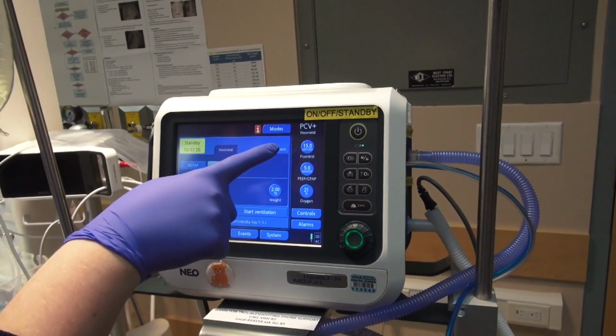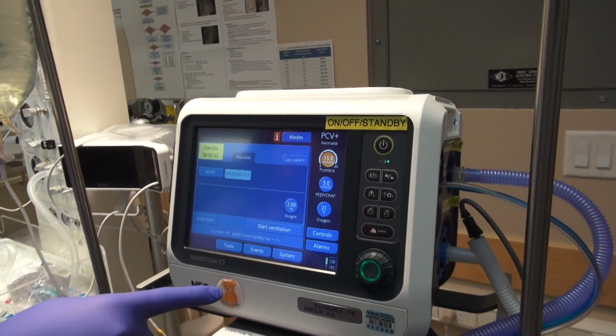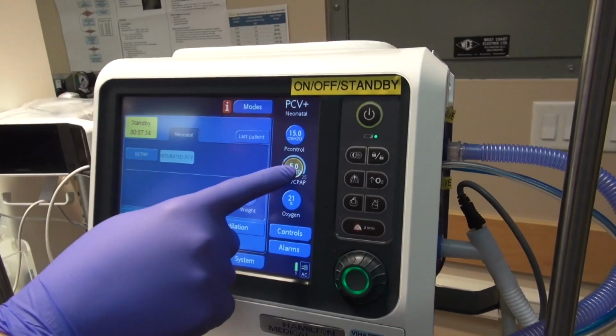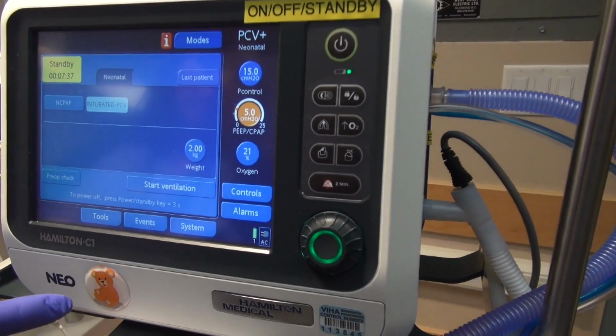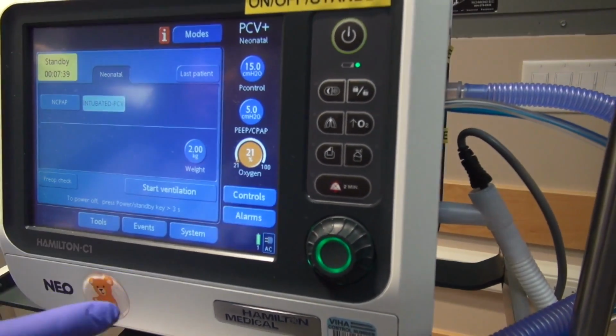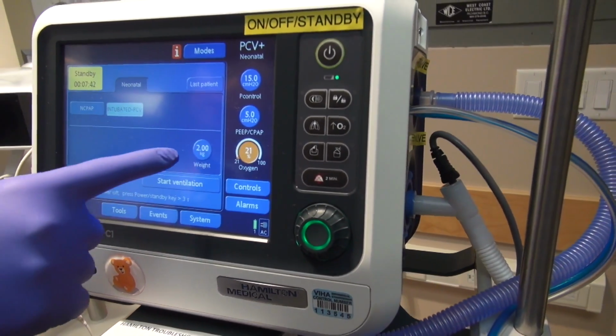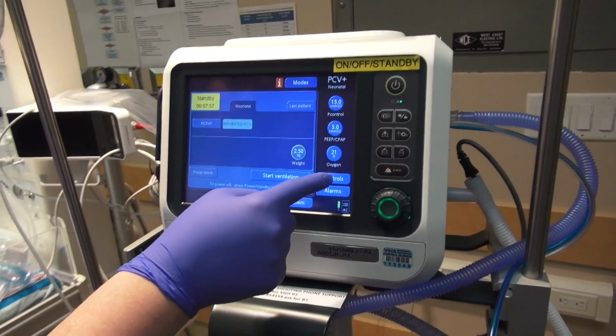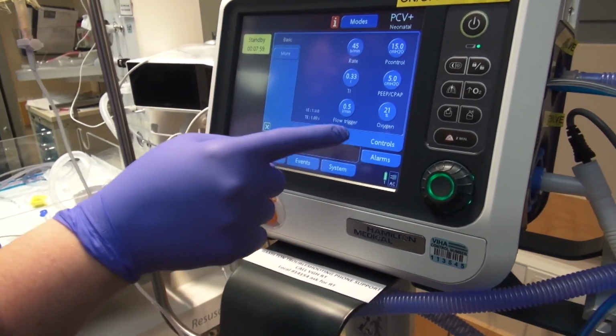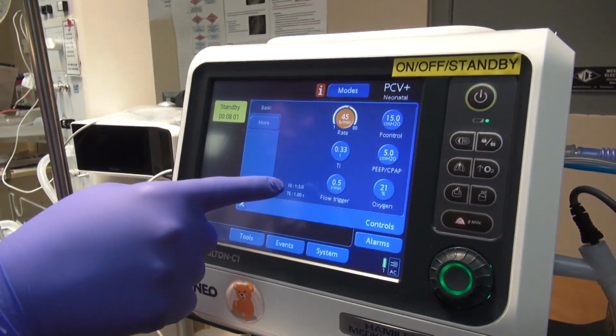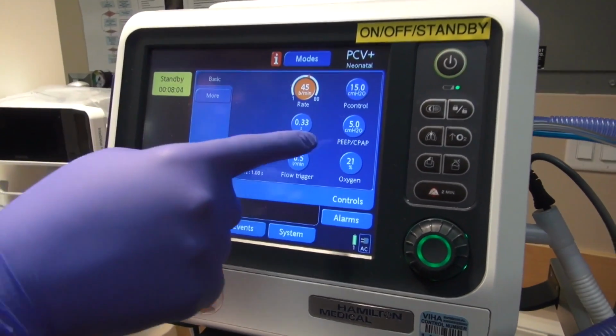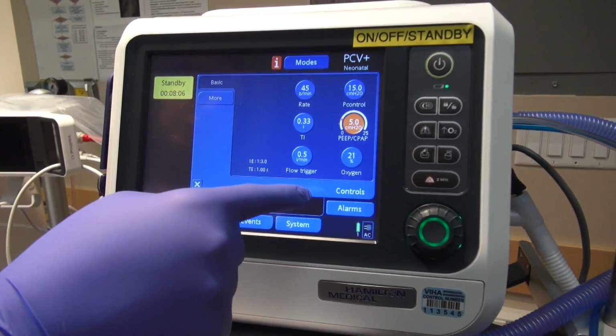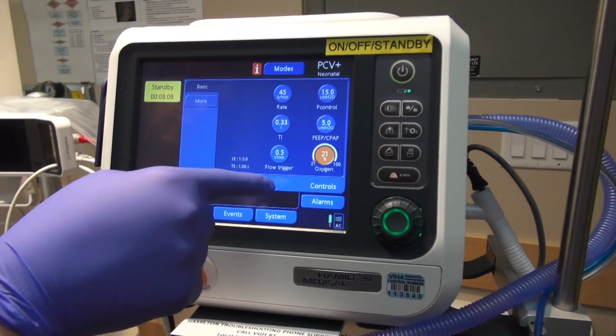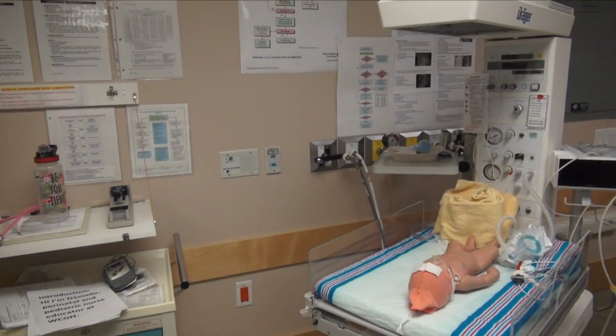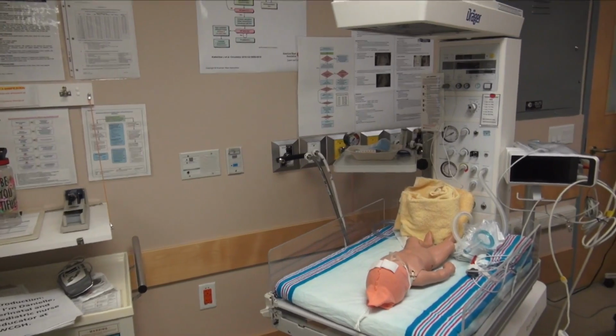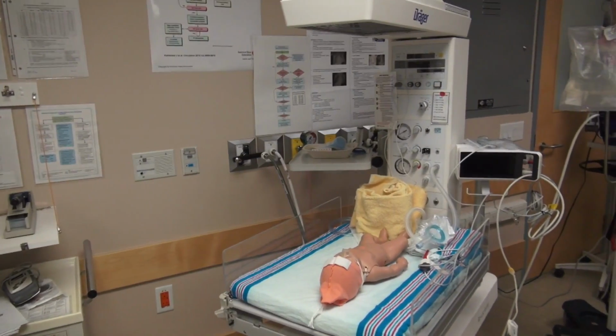Default settings will be to 15 centimeters of water for PIP control and 5 centimeters of water for PEEP control. Oxygen defaults to room air at 21%. To adjust respiratory rate, inspiratory time, hit the control tabs and adjust per direction from the pediatrician. Prior to starting any ventilation, the patient must be disconnected from the ventilator during pre-op check.